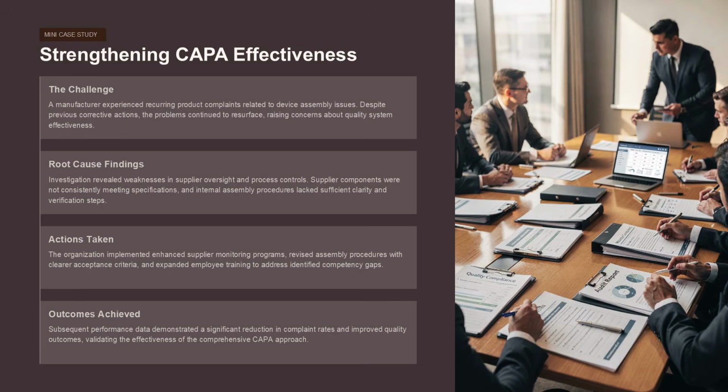The organization implemented enhanced supplier monitoring programs, revised assembly procedures with clearer specifications and accountability, and adopted training to address identified competency gaps. Subsequent performance data demonstrated a significant reduction in complaint rates and improved quality outcomes, validating the effectiveness of the comprehensive CAPA approach.